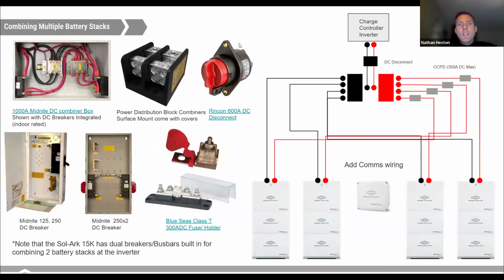Also, if you do need a DC disconnect, be careful. 48 volt rated disconnects are not really rated for the appropriate voltage. A LFP 48 volt nominal battery will actually go up to 56 volts. These Rincon switches, so switches can be a point of failure.